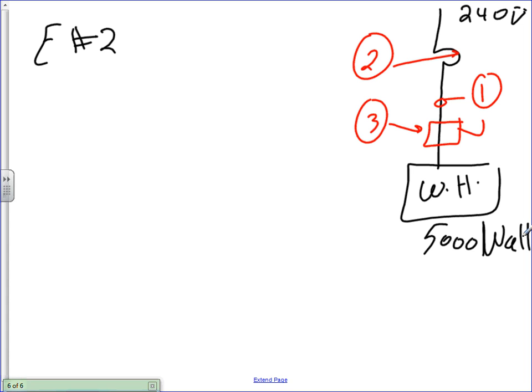Let's go do that. By the way, before I move on, everybody knows, as you move forward, what this is called: a one-line diagram. Every time we have an example, we start with the overcurrent protection device in the panel. We pull a cable, we put a disconnect. Next to the disconnect, we put the machine. Everybody knows what I'm drawing here, and I'm only showing one line. It's called one line. So since this is 240, how many circuit breakers are you going to have? 2 pole circuit breakers. Since this is 240, how many conductors are you going to have? 2 conductors with a ground, right? Everybody understand that without writing it?